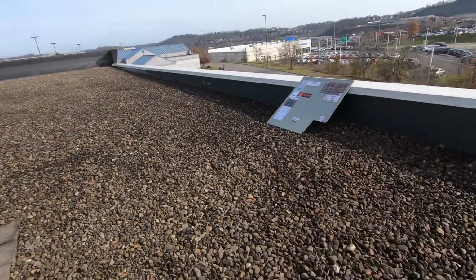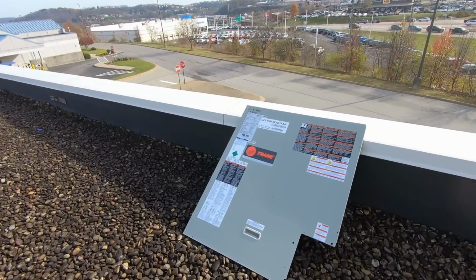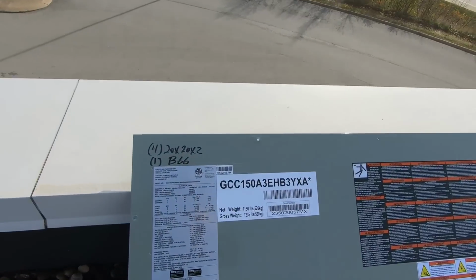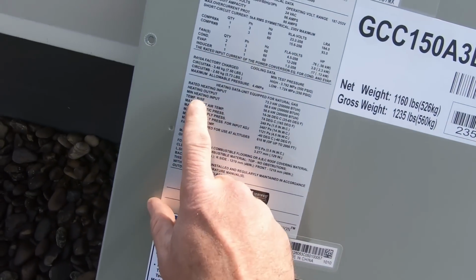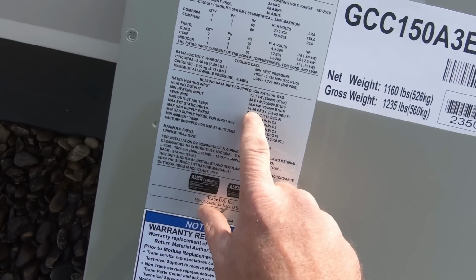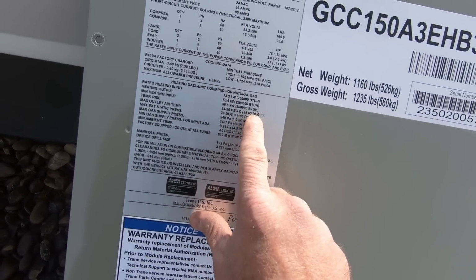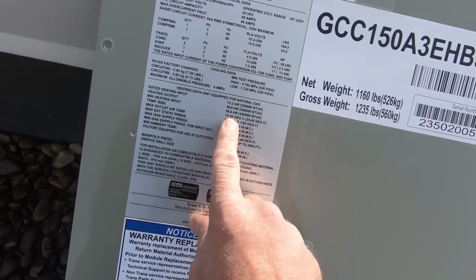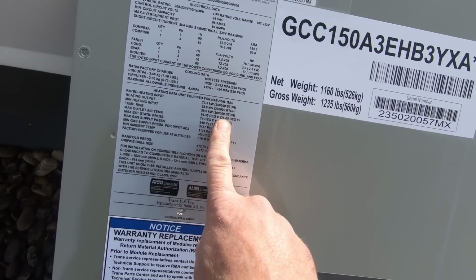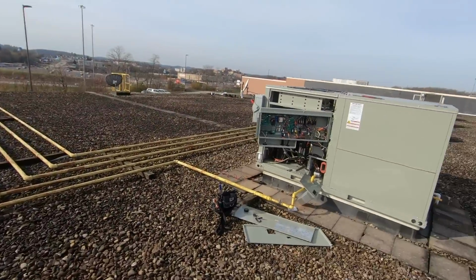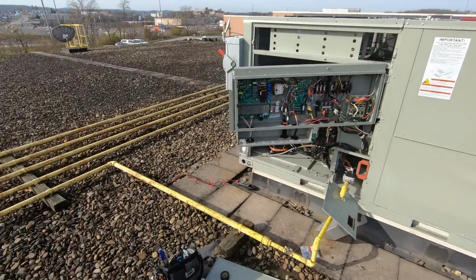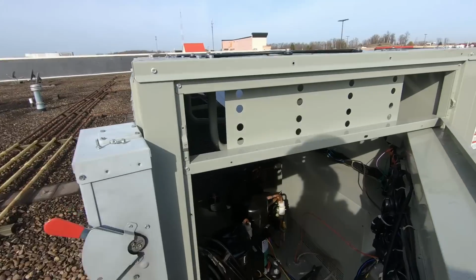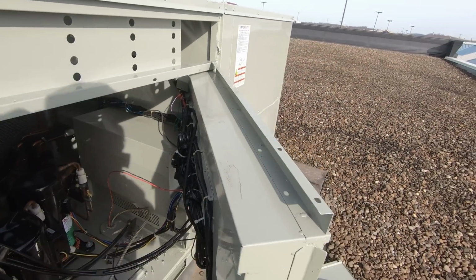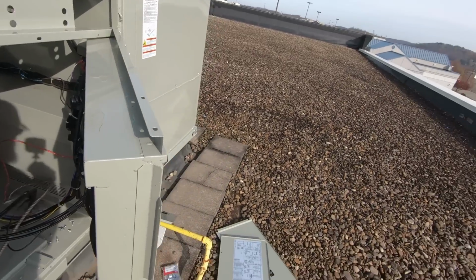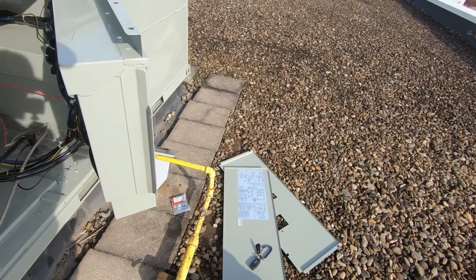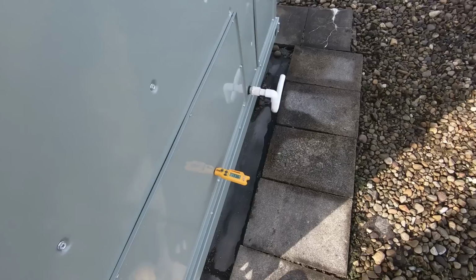Where's my, oh, it's over here. See what my temp rise is supposed to be on this. Oh, let's see. Temp rise, 25 to 65 degrees Fahrenheit, 14 to 36 degrees Celsius. So we need to be between 25 and 65 degrees difference between the supply air temp and the return. So as I button this up, we'll max out our supply air temp and then move it over to the return. It was reading 64 in the store, so we'll see exactly what it's reading.